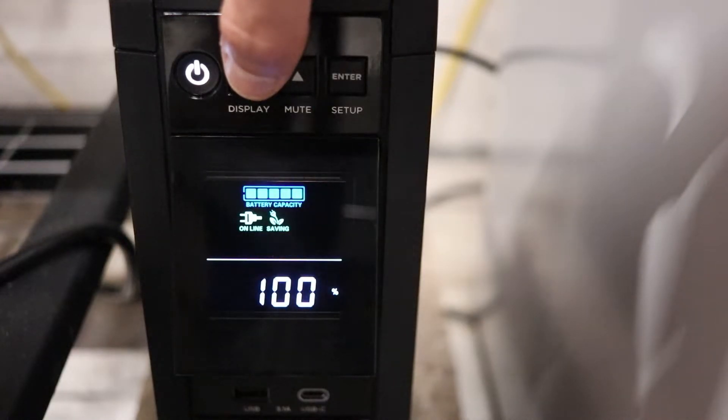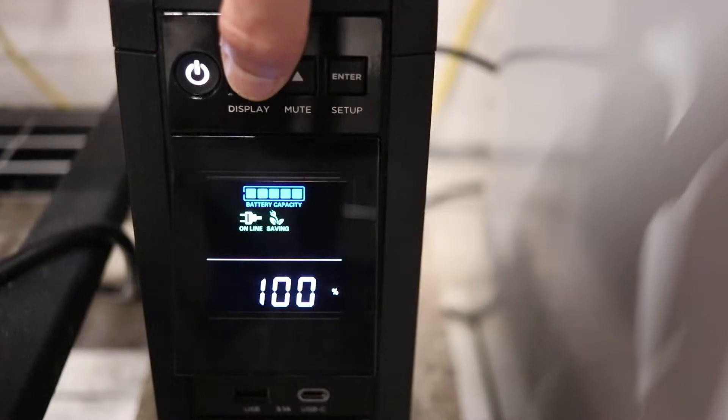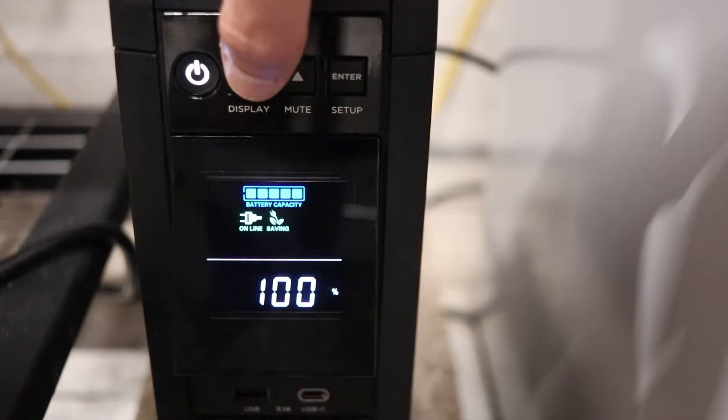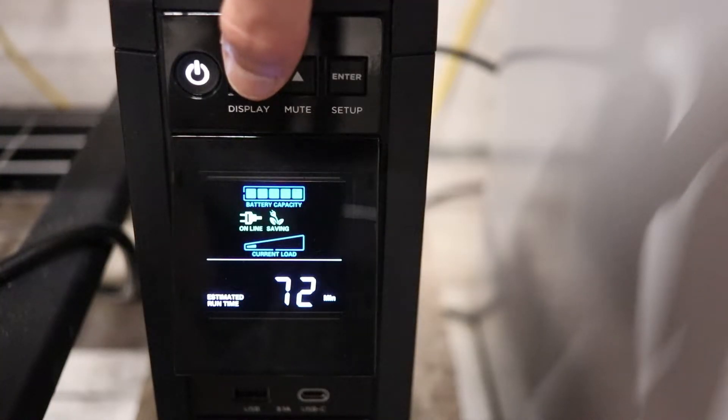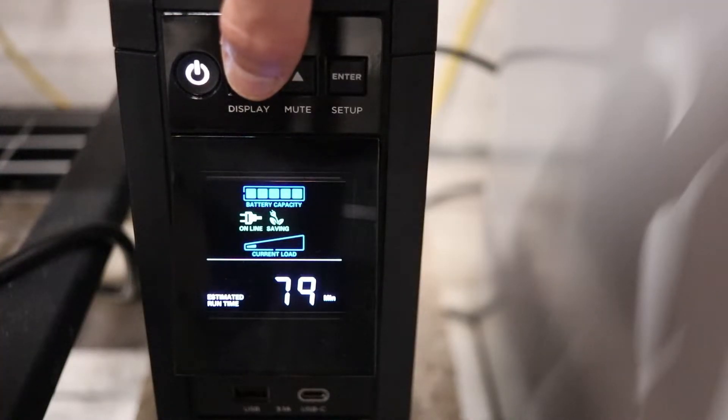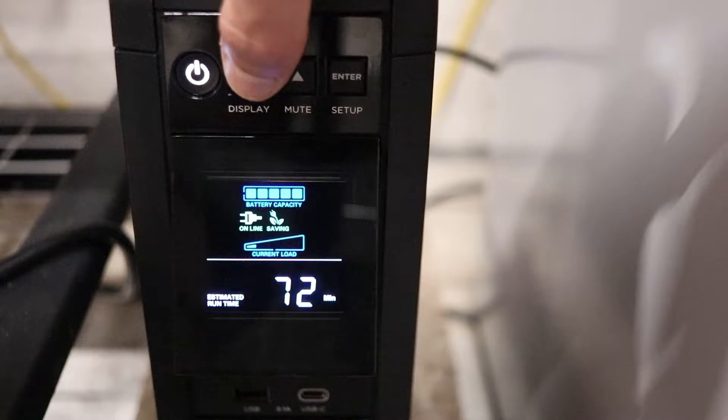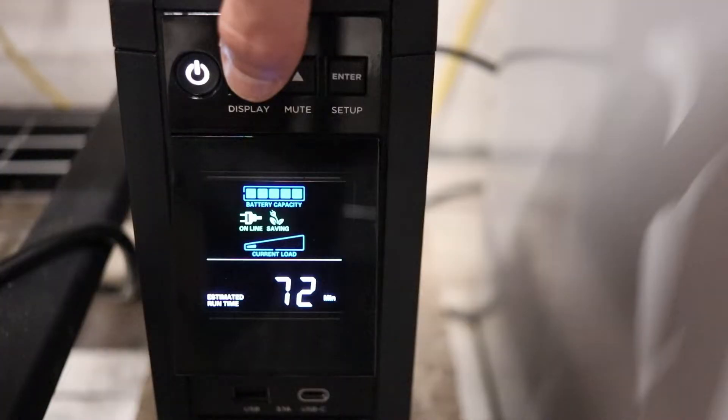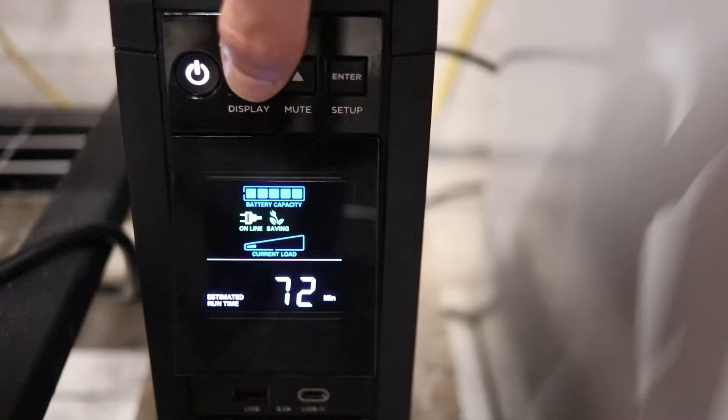Right here, you'll see the capacity in digital form, which is 100%, because right now it's passing power through the UPS unit. And right here, you'll see an approximate run time. If the grid power were to go down, and this would have to run off of battery, it would be roughly about 72 minutes of run time before the battery is depleted based on a 90 watt load.